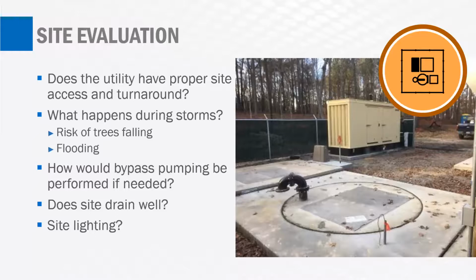Are there bypass pumping considerations at the site? How is that performed? Yeah, typically, if there's going to be an issue at the pump station. Does the site drain well? All of these things need to be considered. And while you're out to the pump station site looking at the pumps, these are things that can be looked at as well.